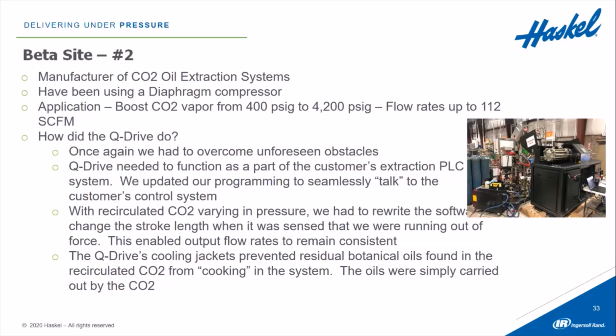QDrive needed to function as part of the customer's extraction PLC system. So what we did was we updated the programming to seamlessly talk to the customer's control system. So the QDrive system talked to the customer's PLC, and it worked out really well. With the recirculated CO2 varying in pressure, which can sometimes happen in oil extraction systems, we had to rewrite the software and change the stroke length when it was sensed that we were running out of force. This enabled the output flow rates to remain consistent. And once again, consistent outflow is what this customer wanted as well. So we had to make sure we were doing things the right way.